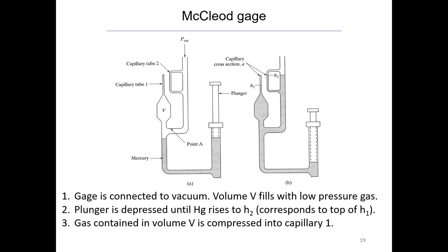The gauge is connected to a vacuum right here; the vacuum pressure comes in and fills volume V with that low-pressure gas. Then the plunger is depressed — that's when we transition to state B — and it's depressed until the mercury rises to h₂, which corresponds to the top of h₁. All that volume of gas gets compressed into the capillary, and because you're compressing that very low-pressure gas it reaches a higher pressure, so you can now get a measurable fluid column.